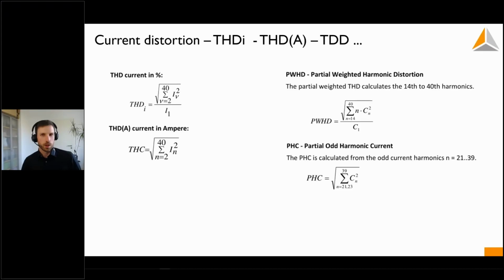When talking about current distortion, there are other values as well. There's a total harmonic distortion for the current in percent, and there is also a total harmonic distortion of the current in amps. I will focus on these two in a minute, but I also will show that there are more measured variables in different standards. For example, the industrial standard 61000-2-4 also included the partial weighted harmonic distortion.